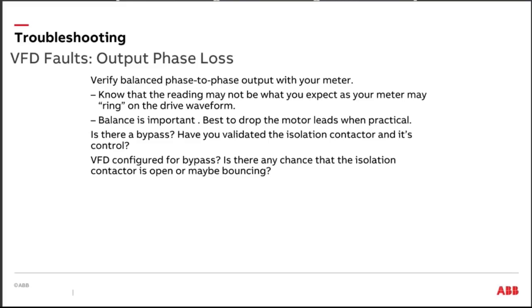So if you do have bypass, let's make sure nothing's going on with the isolation contactor there. If you do have bypass, historically, when I started up a drive bypass package, I always like to bump the package in bypass first and just notice the direction of the motor. Then I would bump it with the drive and make sure the motor is running in the same direction in bypass and in drive. Really important, okay?